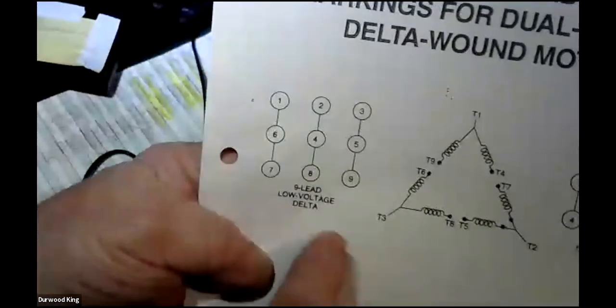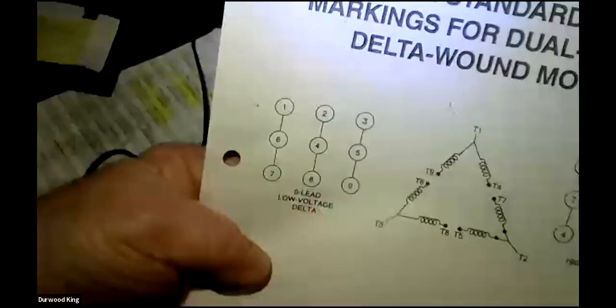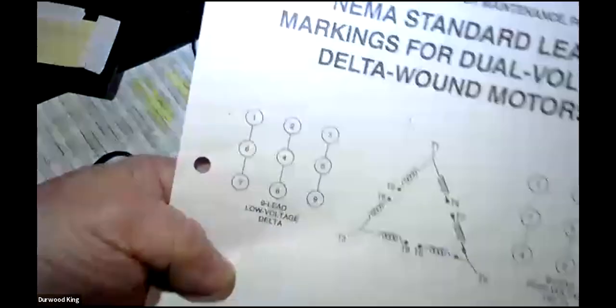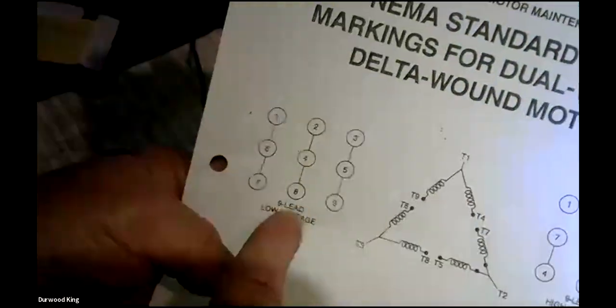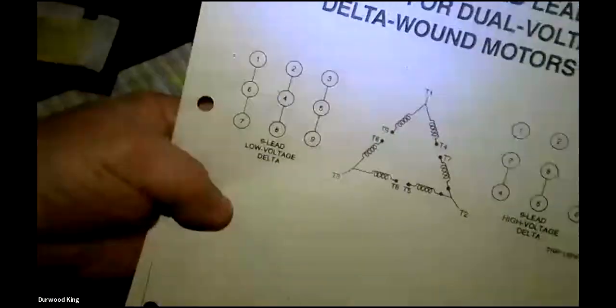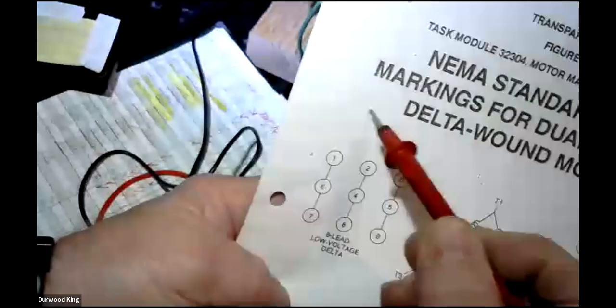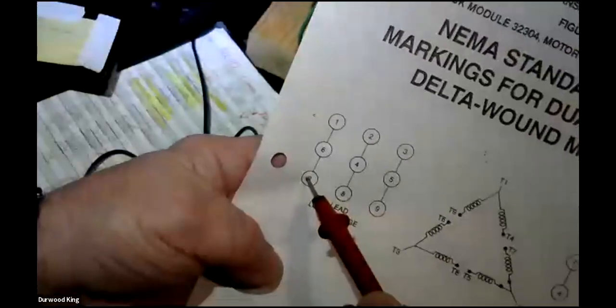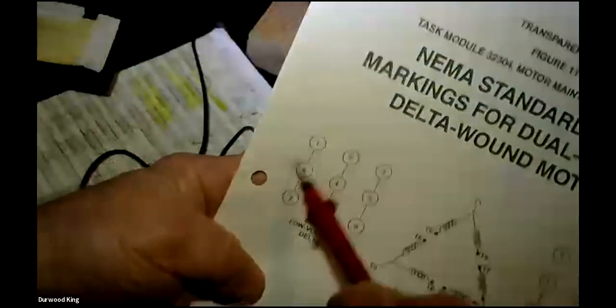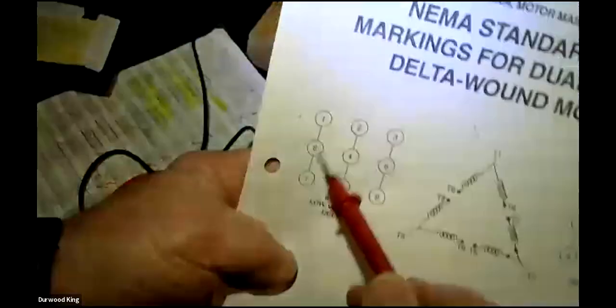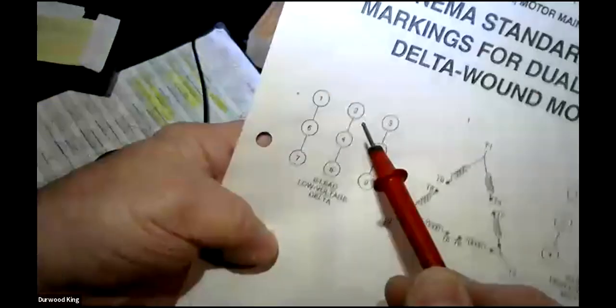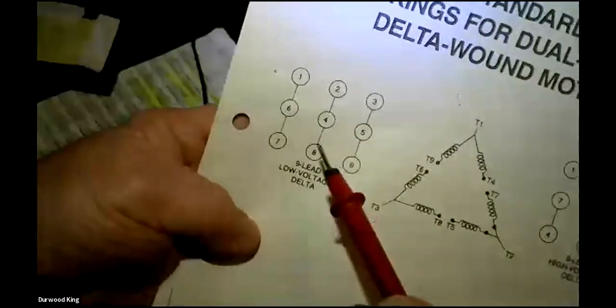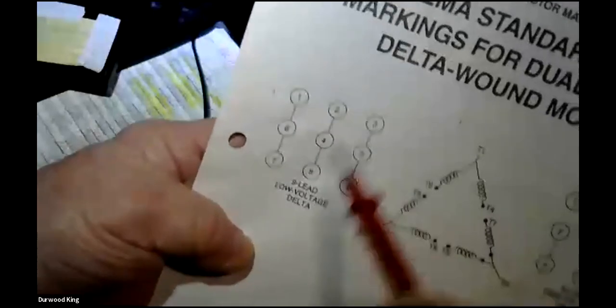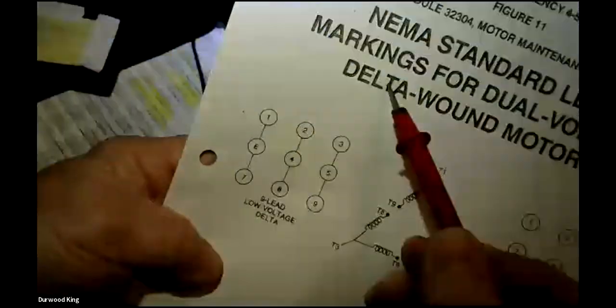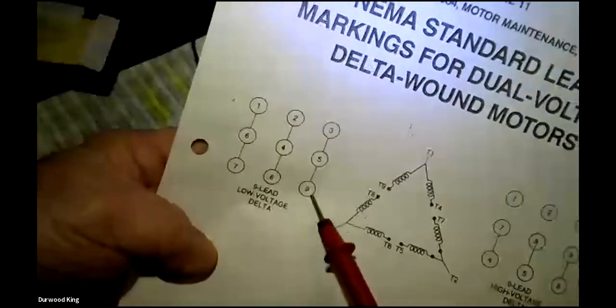Low voltage Delta, when you're doing it at 230 or 240, look here. This is the one that's so different from anything else. You take your incoming line coming from the starter, and it connects with 1, 6, and 7 at the same time. So there's actually 4 wires together here in the conduit head for that line. Line 2 from the starter meets with 2, 4, and 8. You get 4 wires here, including the incoming. Line 3 comes in, it hits 3, 5, and 9.